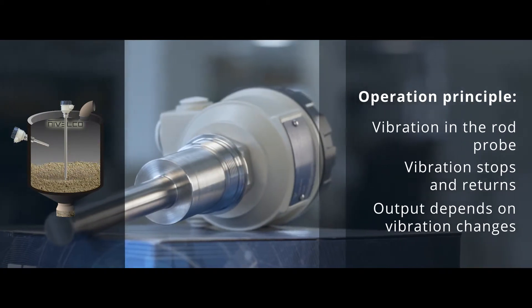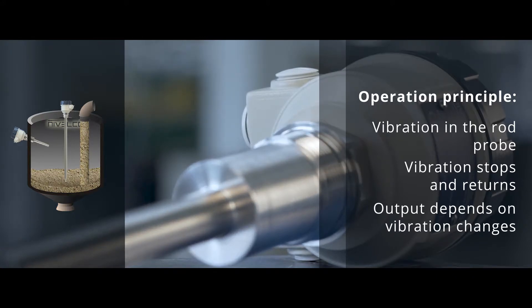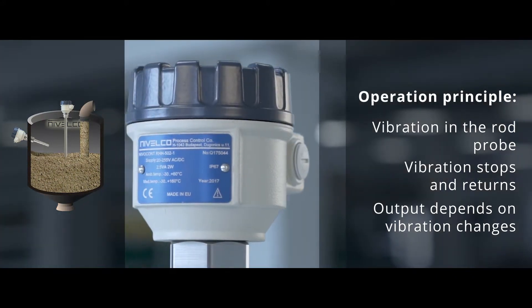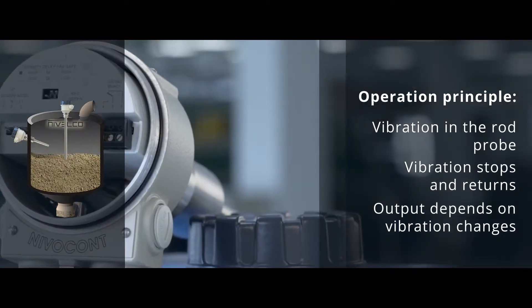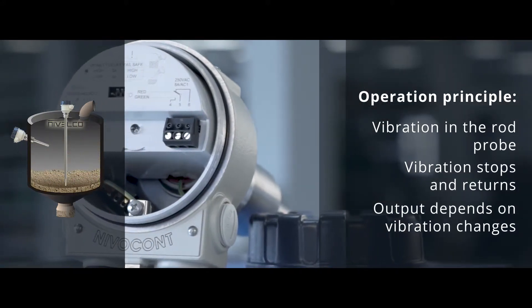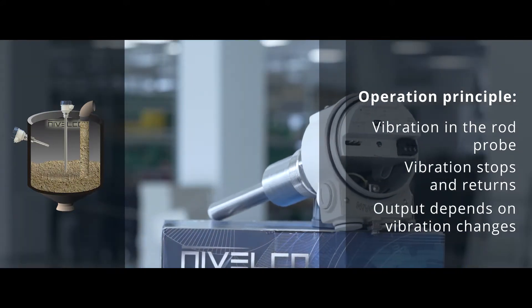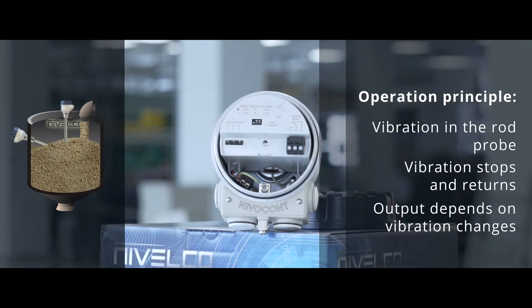Operating Principle. The electronic circuit excites a vibration in the rod probe. When the medium reaches and partially covers the rod, the vibration stops. When the material level falls, the medium leaves the rod and it returns to vibrate freely. The electronic senses the change of vibration and creates an output signal after a selected delay.